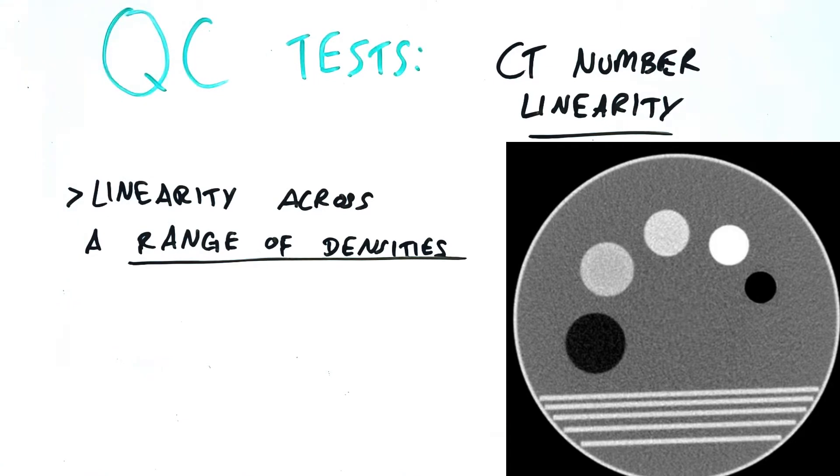That is, if we increase the absorptive properties across different types of tissues in a linear fashion, does the measured Hounsfield units properly respond in a linear fashion? CT number linearity should be tested monthly.